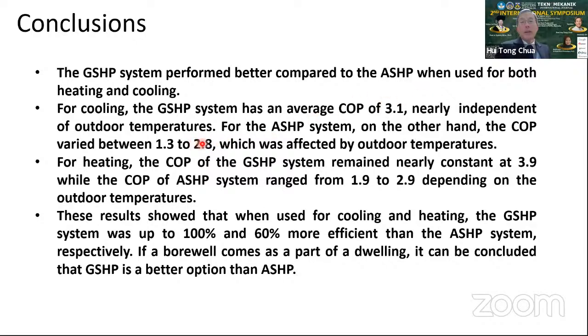So you can see, yes, when the outdoor air is warm, it can get close, but that misses the point. It is when the outdoor is cold that we require that. So it can be up to 100%. I wouldn't say it's 300%, because this is a pretty cold temperature. So typically it can be up to 100% more efficient for the ground source heat pump, or GSHP system, in the cooling mode. Now in the heating, you can see here, the ground source heat pump remains at a very high COP of 3.9 compared to 1.9 to 2.9.